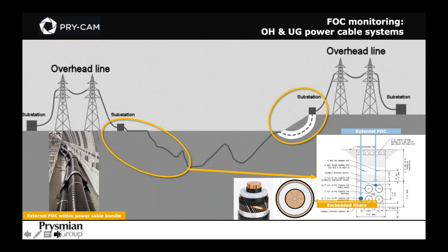When using fiber optic cable externally, we have the option to either utilize existing telecommunication fiber optic ducts or dedicate a separate duct for a DTS DAS sensing technology conduit. When using embedded fibers, we will place fibers in the screen or sheath of the high voltage cable, or we'll use external fiber optic cables as part of the power cable bundle.